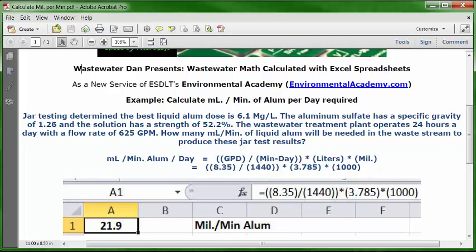Let's look at how to put all this into an Excel spreadsheet. Go to an open spreadsheet, put your cursor in C1 and type the description: milliliters per minute of alum. Go to A1, format it as a number with one decimal, make it bold and centered. In the formula bar, type: equal sign, two open parentheses, 8.35, close parentheses, division key, open parentheses, 1440, close parentheses, multiplication key.